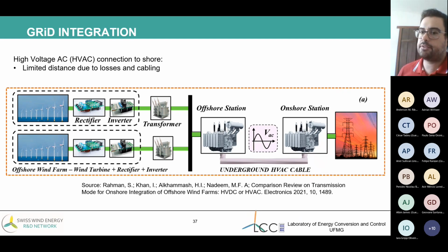As we have important distances between the wind farm and the grid connection on land, high voltage transmission is normally used. The first concept is a high voltage AC connection to the shore. I have here the turbines, the generators, and the power converter, divided into a rectifier and an inverter, and a transformer inside the grid. For each one, this is similar to onshore. I have the offshore station to increase the voltage to high voltage AC to connect to the onshore station.